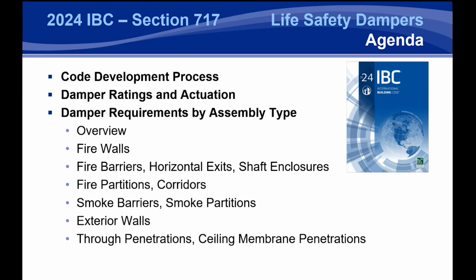We're going to go over the agenda for this presentation briefly. We'll talk a little bit about the code development process, damper ratings and actuation, whether they're fire dampers or smoke dampers, and then the bulk of the presentation will go through different fire barriers and the minimum requirements in Section 717 for protecting duct penetration of those barriers, whether it's a smoke-rated barrier, a fire-rated barrier, or maybe a combination of the two.